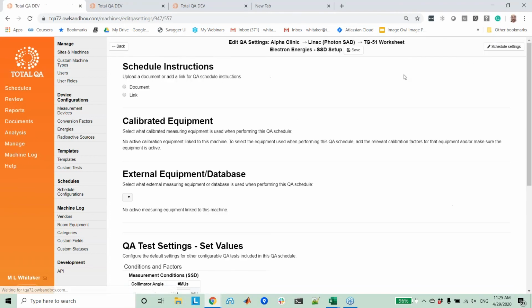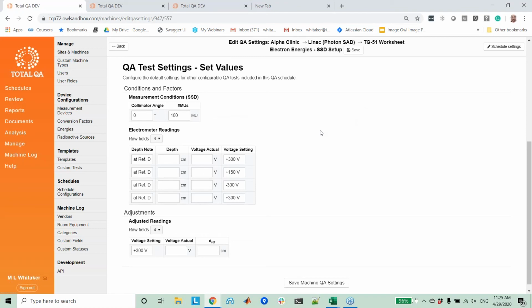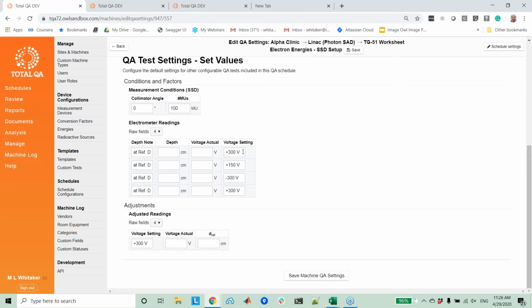So once you've added that, there are some QA settings that you may want to set up: how many MUs you plan to shoot on this, if you don't want to fill it in each time, and what the collimator angle is, so that those are pre-filled, and then what your voltage settings are going to be, in this case in the electrons, at your positive high, your positive low, and your negative high. It is expecting the order to be either positive or negative high first, then low second, and then the opposite sign high third. The other thing that you can set up is how many readings you're expecting to take.